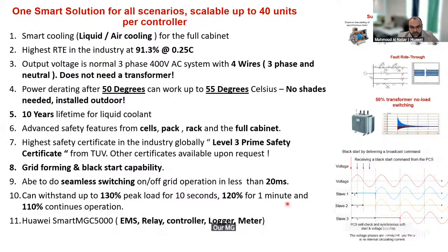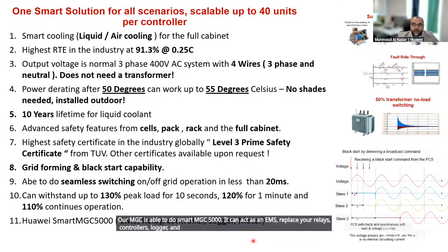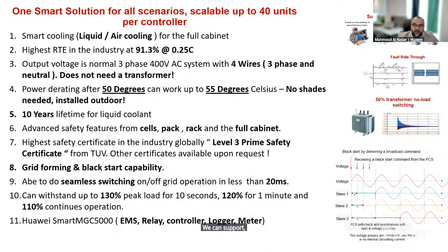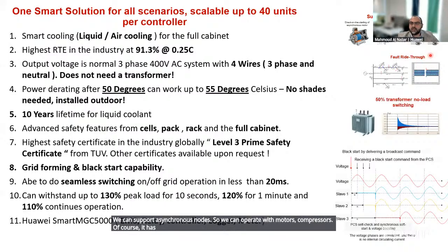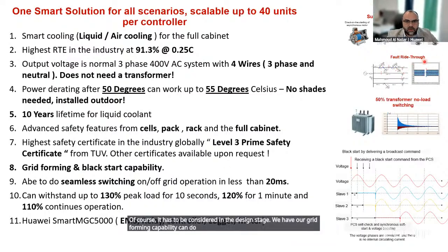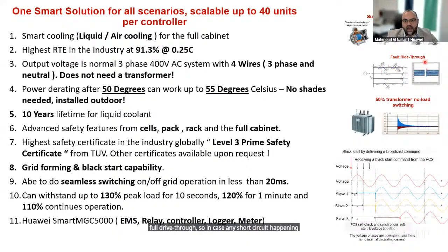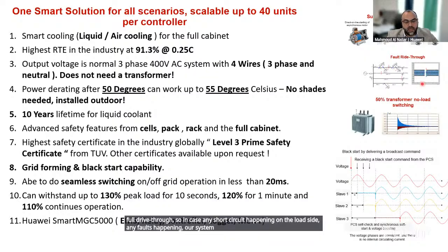Our MGC is the Smart MGC 5000. It can act as an EMS, replacing your relays, controllers, logger, and meter. We can support asynchronous loads, so we can operate with motors and compressors. Of course, it has to be considered in the design stage. We have grid forming capability that can do full ride-through. So in case any short circuit or any fault happens on the load side, our system will ride through and make sure we still have continuous power being delivered.